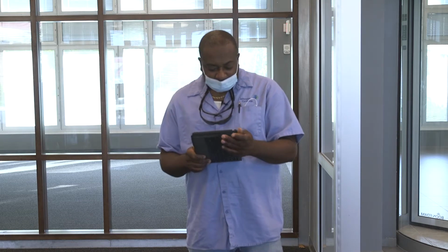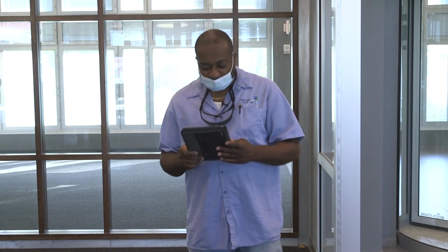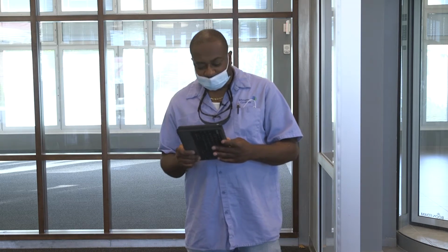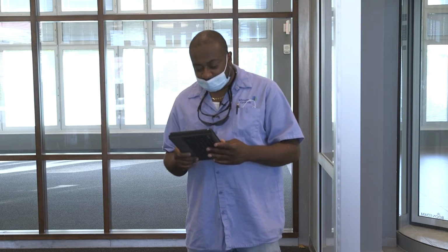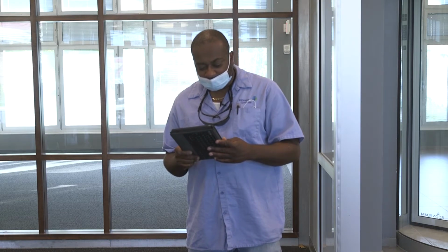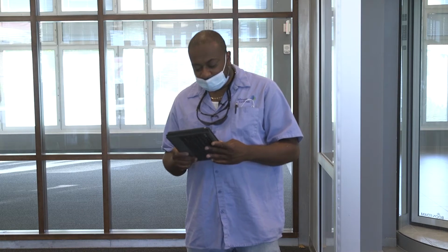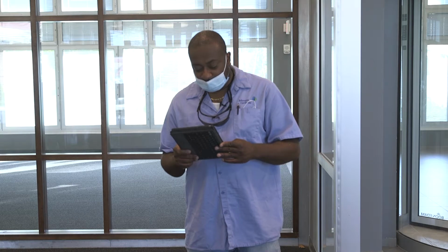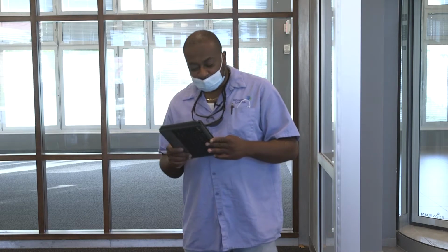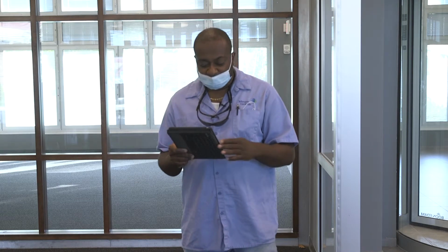So you set the room thermostat fan switch to the on position, a 24-volt signal is provided to the G1 terminal directly from the thermostat or from the condenser, which is a heat pump. That closes the coil of the fan motor relay, which is BR1.